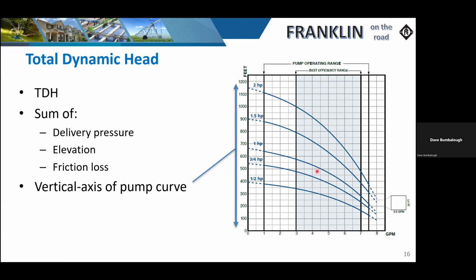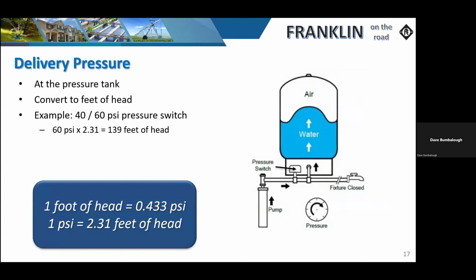Okay, so as we start adding up for our TDH, we're going to look at delivery pressure. We're going to look at elevational changes. We're going to look at friction loss. And then once all that's added up, that basically transitions into what horsepower it's going to take to move this volume of water. As we go through this exercise, you're going to see that we can get in some trouble once we get past a couple points I want to make first, and then I'm going to harp on pipe sizing, which is very crucial. And that can lead us into some issues.